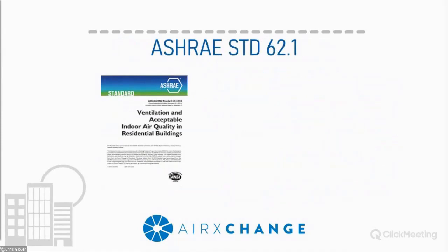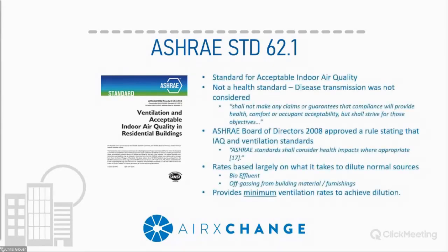So what determines the ventilation rate in commercial buildings? ASHRAE Standard 62 is the ventilation standard for acceptable indoor air quality in buildings. I'd like to state that the standard itself is not a health standard. Disease transmission was not considered when developing these rates. It strives to provide guidance that provides health, comfort, and occupant acceptability, but doesn't guarantee it.